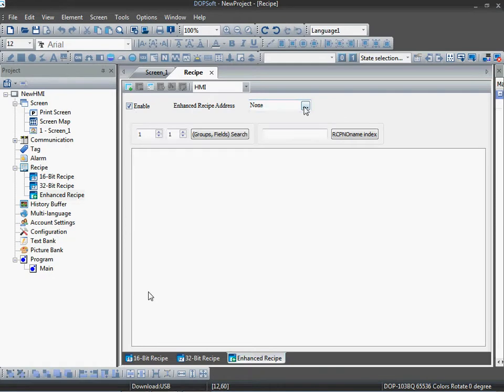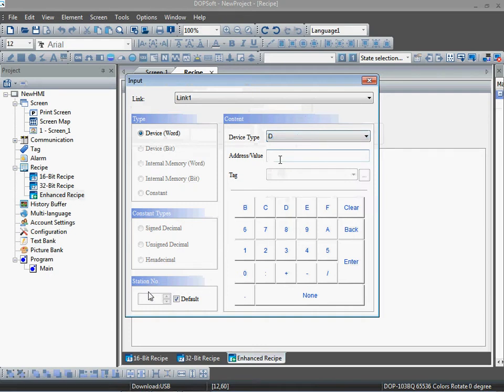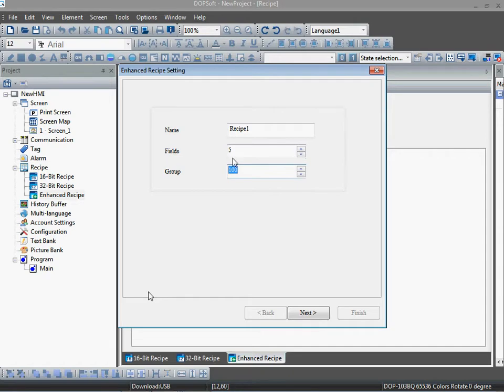Click on enable enhance recipe. Give here one register address — I am giving D200. You can give any address for the register. Click on new recipes, give the name for the recipe: Recipe One. For fields, I want five fields, so enter five. And I want 100 programs, so I enter 100.